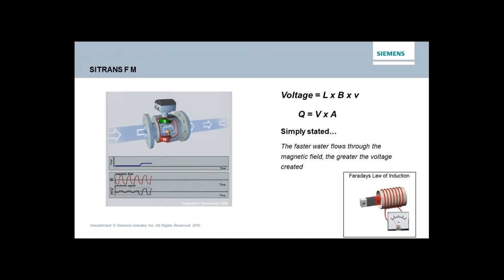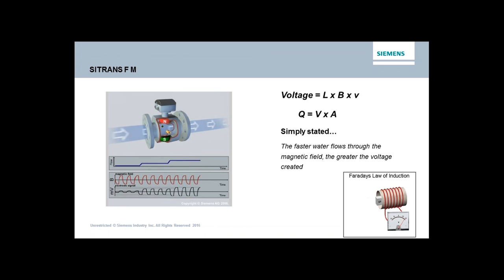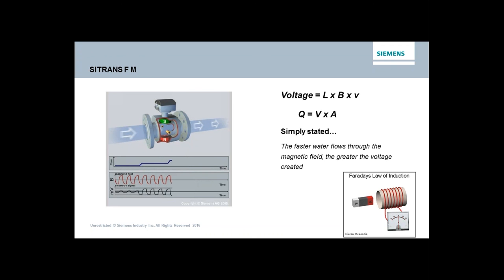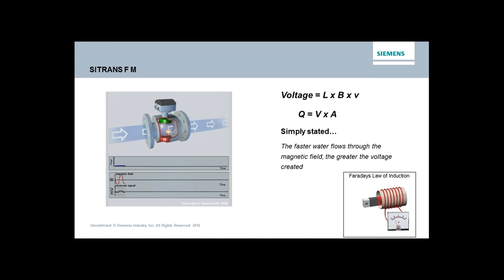If you look to the left, you'll see a typical mag meter in operation — the magnetic field is created, and then you've got the conductive material passing through it. What's interesting to note about a mag meter is that it doesn't matter what the conductivity of the material going through the meter is, as long as it meets the minimum threshold, which is traditionally 5 microsiemens per centimeter for most mag meters. As long as your conductivity is at that level or higher, the meter is going to work, and if the conductivity changes, it doesn't matter.